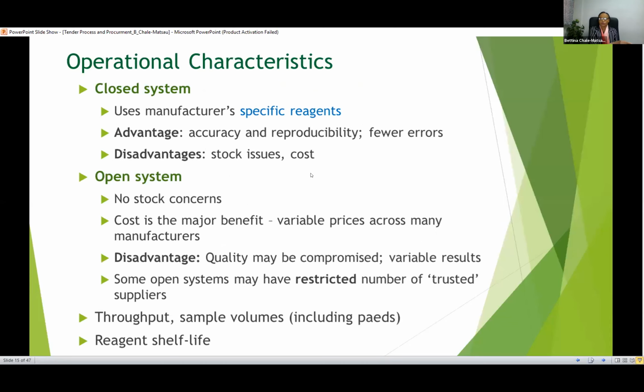Other issues to think about when planning are the operational characteristics, like the closed system. Manufacturers that use a closed system are essentially saying to you, use our own reagents. The advantage of the closed system is that accuracy and reproducibility are almost guaranteed, because you'll have fewer errors, as these have already been tested. However, the biggest issue here will be the cost. They tend to be very expensive, and you might even have stock issues.